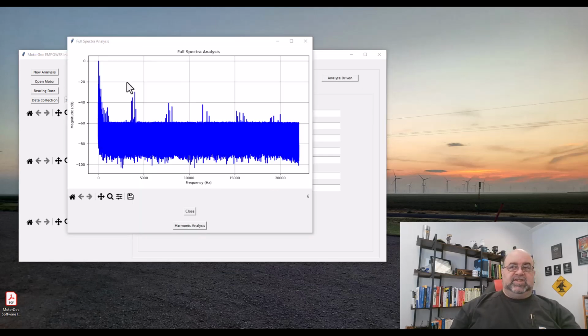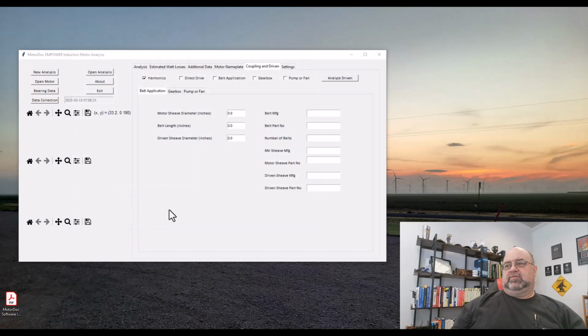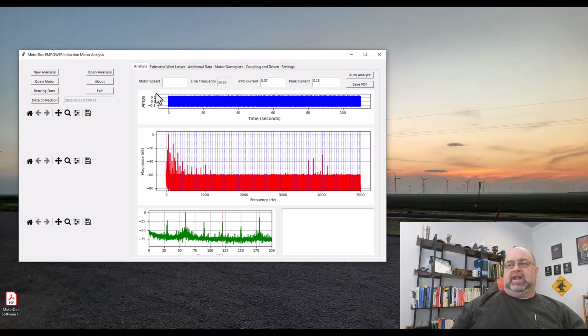As you can see, all that noise is still there. The harmonic content's still there, it's just got noise masking most of it. So I'm not going to go into the rest of that part. Let's finally look at ground on the machine. Now, this is a direct measurement off the ground coming back from the motor, going straight to the VFD, the common point. So I'm going to pause and open the data, and then I'll show you.